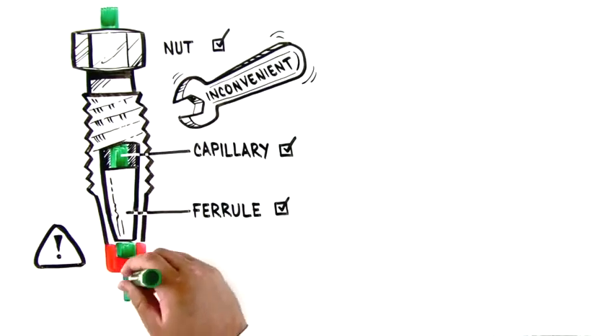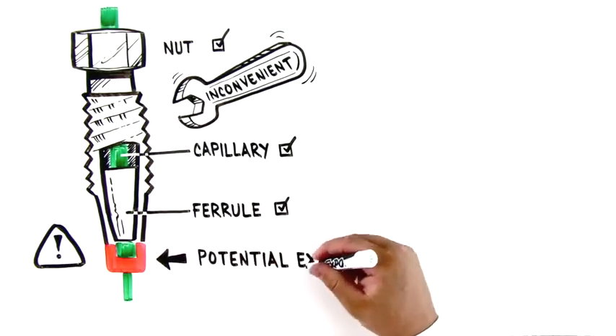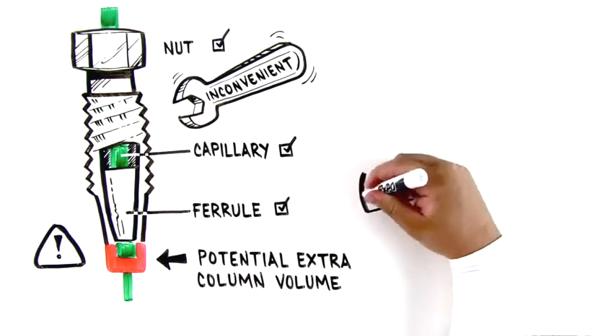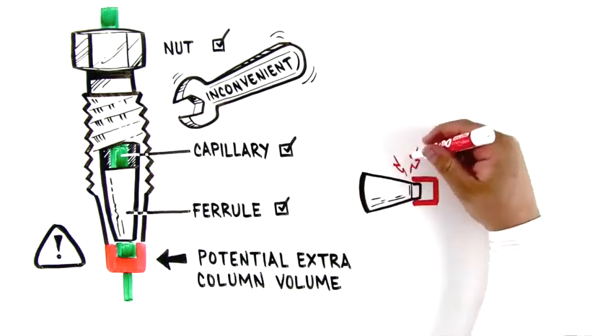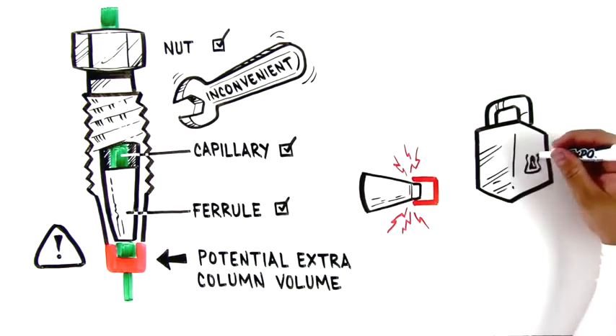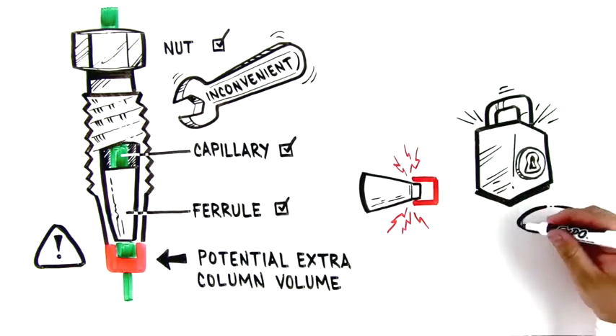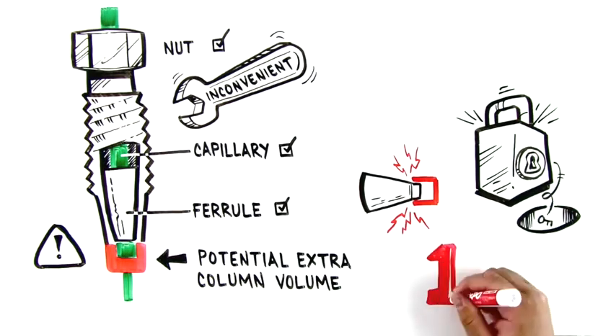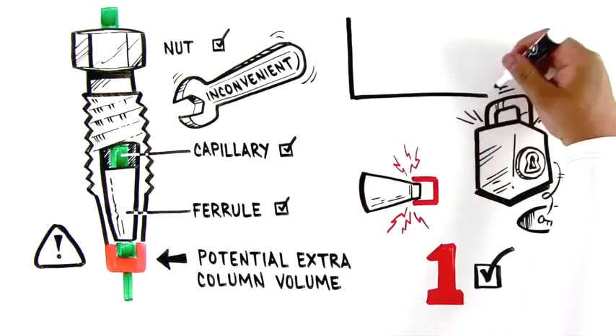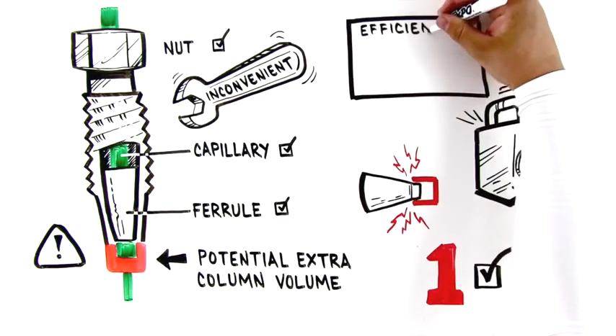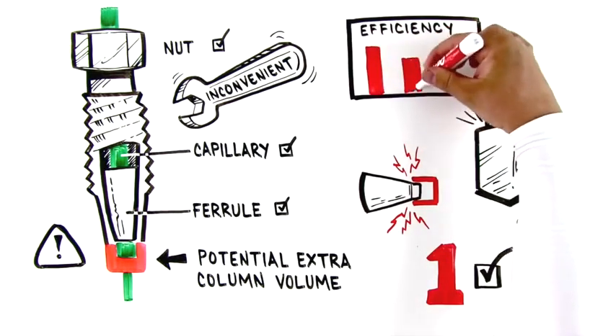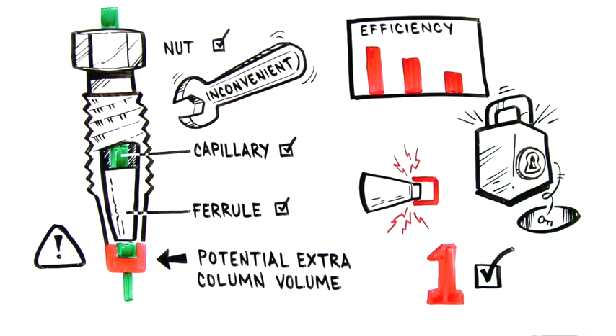Ferrule-based fitting systems are also prone to errors such as incorrectly positioned ferrule. Additionally, once a ferrule is wrongly positioned, the error can't be corrected. A ferrule-based fitting therefore only fits best on exactly the column or valve it's first connected to. This bears the inherent risk of unwanted void volumes in the fluidics, which will immediately negatively impact the efficiency.